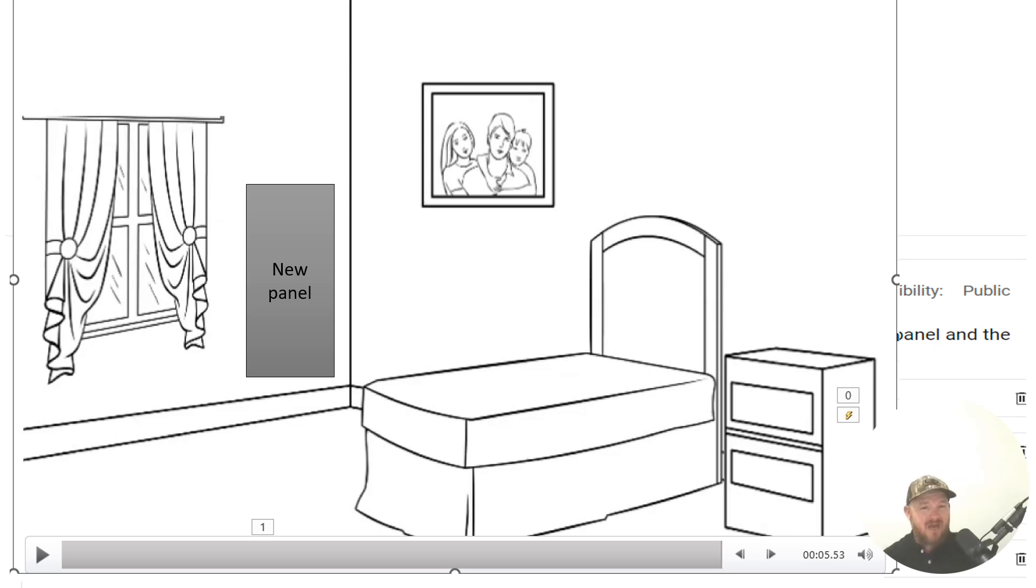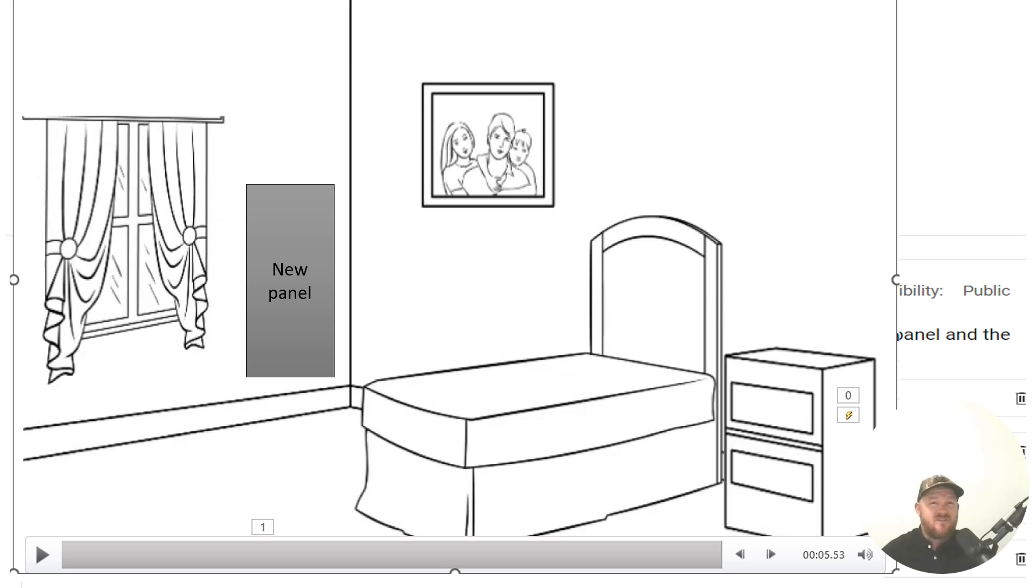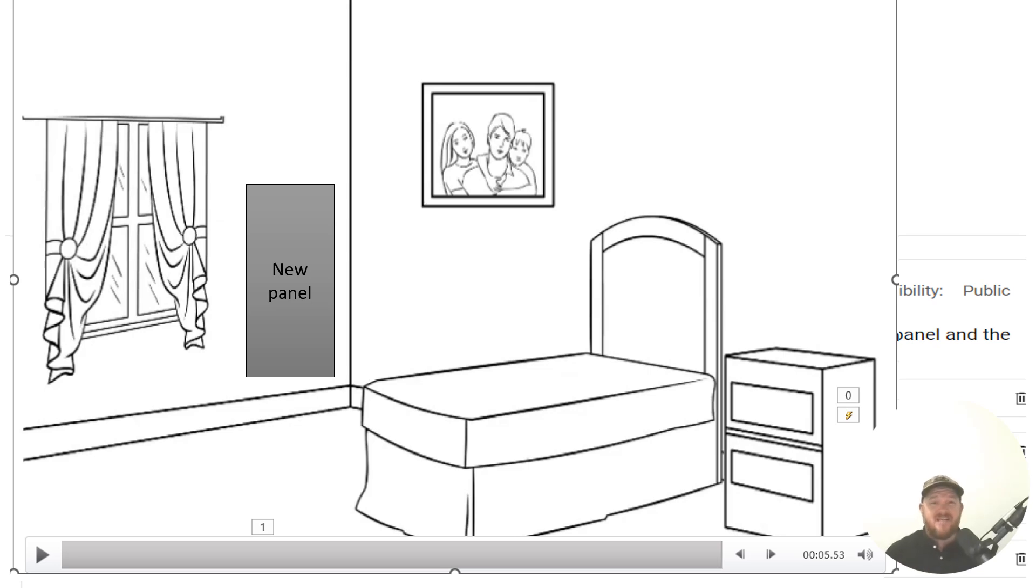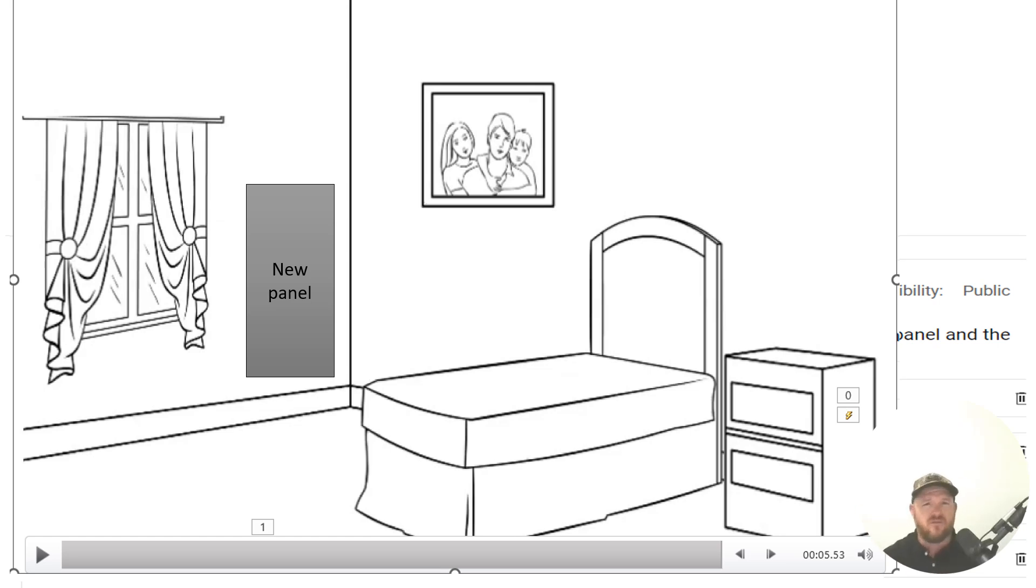They do not want any drywall repair at all. You try to talk them out of it. You let them know it's going to have to be basically back on the floor. But the question is, are you allowed to do it and what does the NEC have to say about it? So the answer is yes. In this case, you could put that panel back where it's at as long as you met all the other codes.